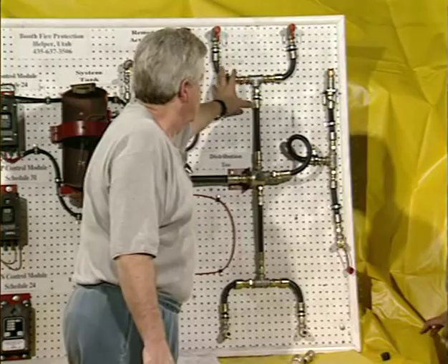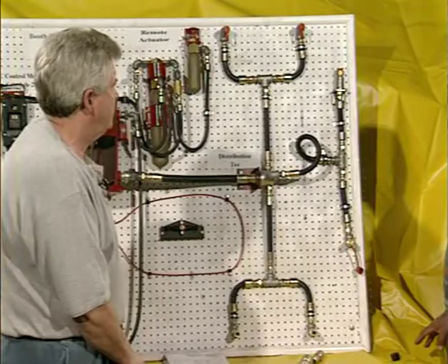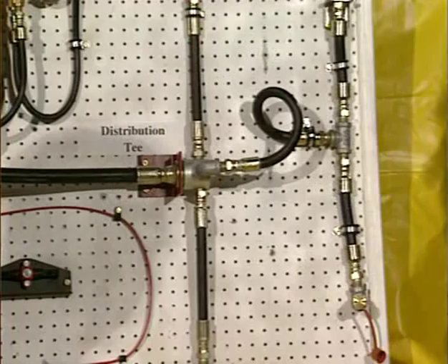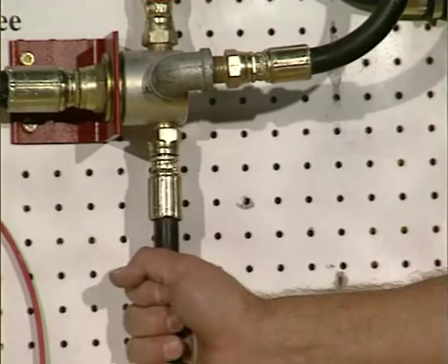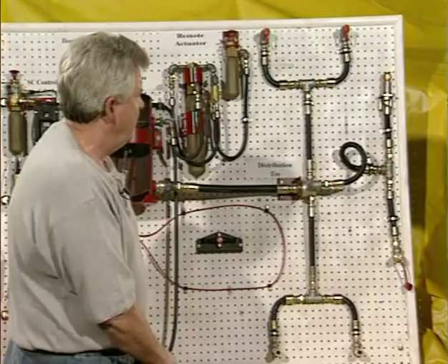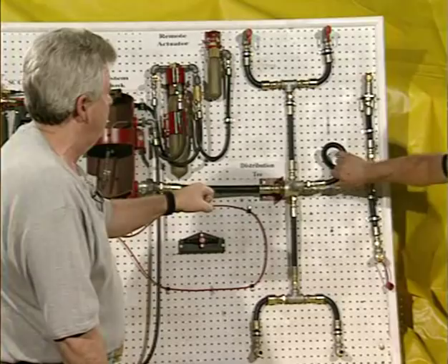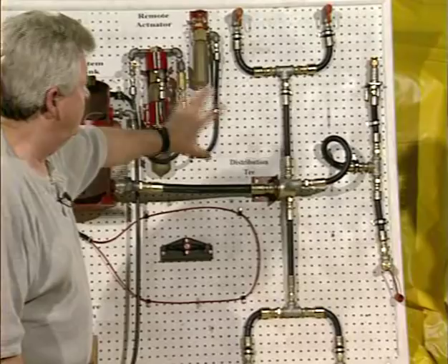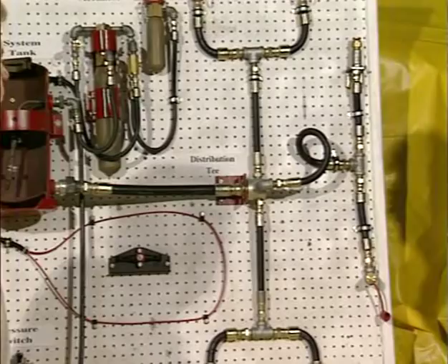The three-to-one ratio means: if the total length of one group of three hoses is three feet, the maximum on the next group of hoses can only be nine feet. If needed, you can wrap a hose to make up the difference and achieve your three-to-one ratio. The fittings used are all swivel fittings with an O-ring inside — inspectors may notice they feel loose and move, but that's by design. The O-ring built inside seals them. Swivel fittings are used for easier installation and easier disassembly, so if a hose breaks, you don't have to dismantle the whole circuit.